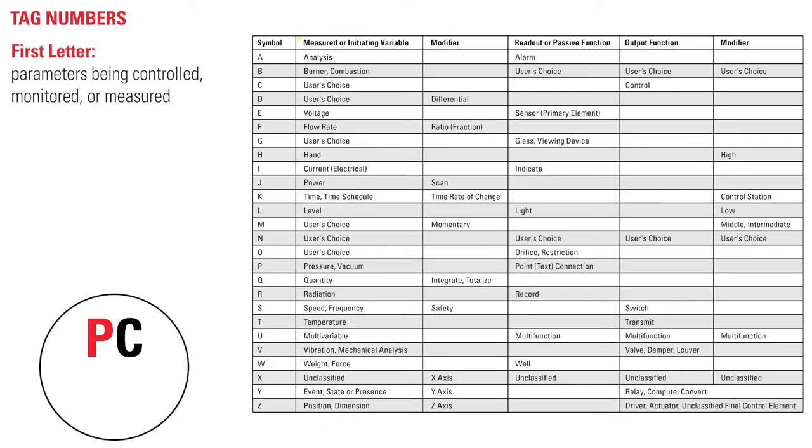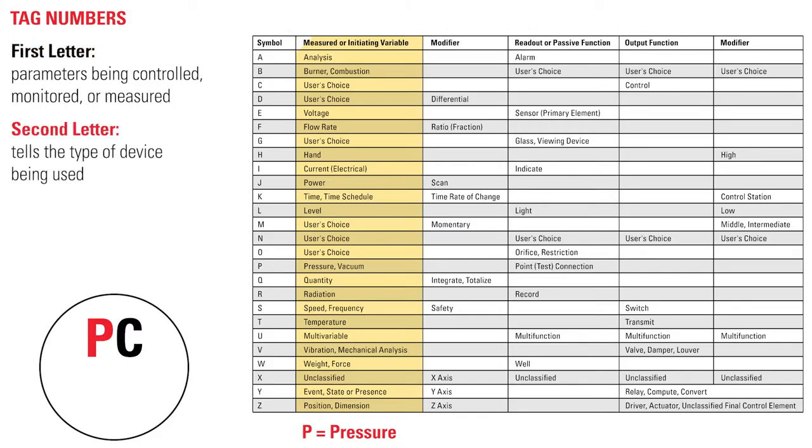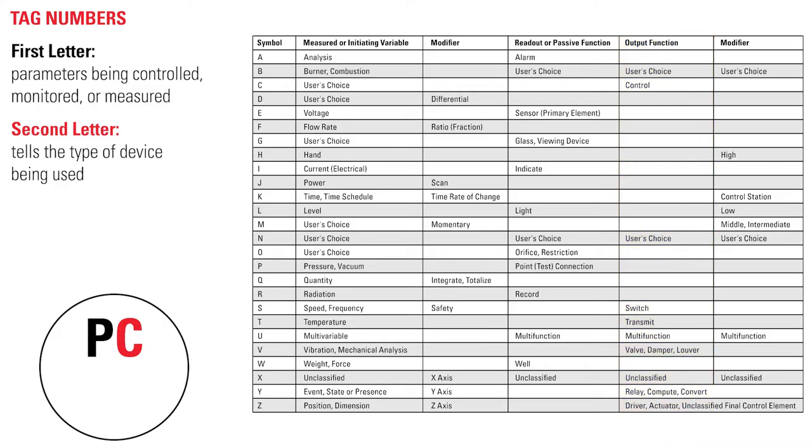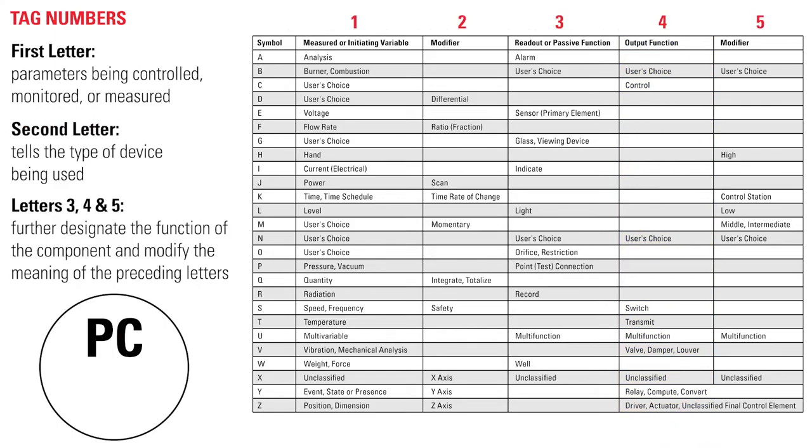The first letter indicates the parameters being controlled, monitored, or measured. The second letter tells the type of device being used. There can be up to five letters used to further designate the function of the component and modify the meaning of the preceding letters.